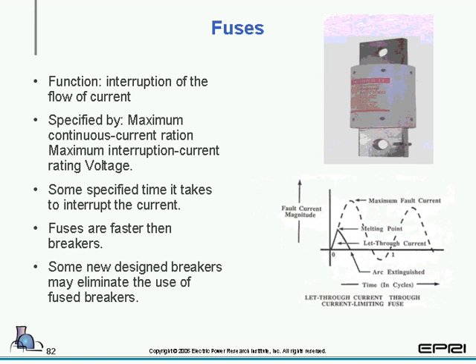Some specified time it takes for the interrupting of the current. Now the fuses are faster than breakers. Some newer design breakers may eliminate the use of fused breakers. And you'll see we have a picture of a fuse, and you'll also see a little chart that shows the let-through current through a current-limiting fuse. Now, when you get to the maximum fault current, which is a dotted line up above, some breakers may actually trip open in a cycle or more than one cycle.